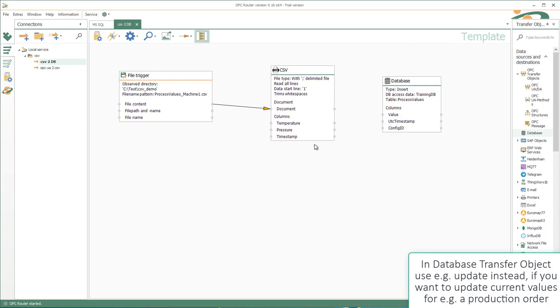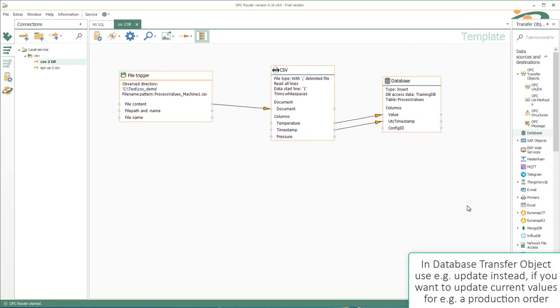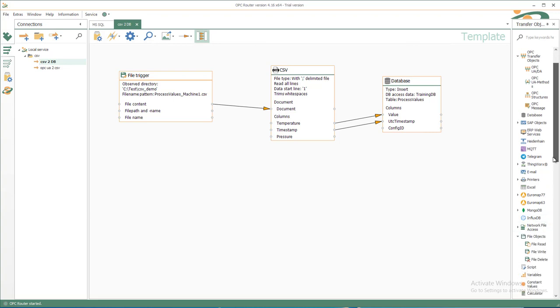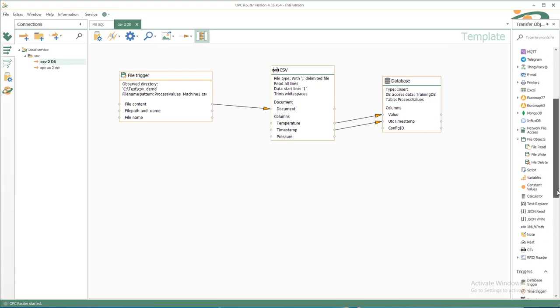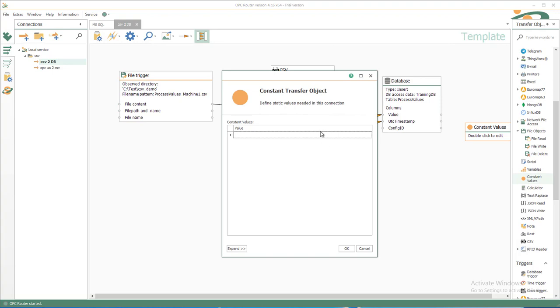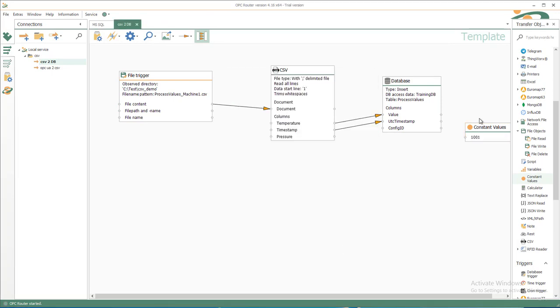So we have the temperature in this example as value, the timestamp as UTC timestamp, and the config ID can be a constant value. So we have the constant element on the right, constant values. Just insert the value 1001 for machine 1 temperature process value and write it to the config ID.